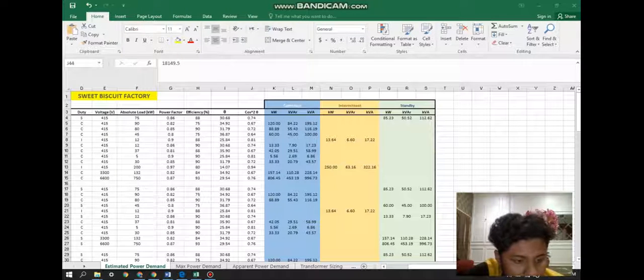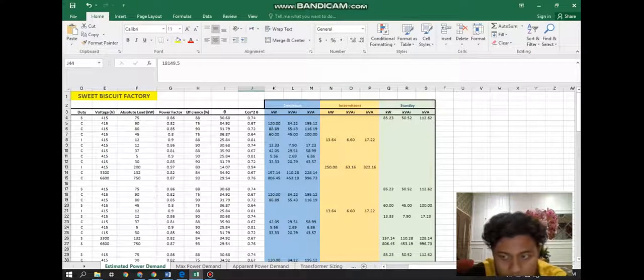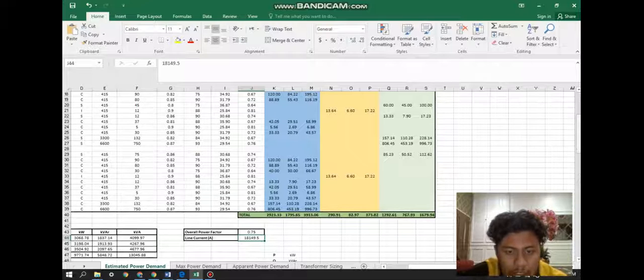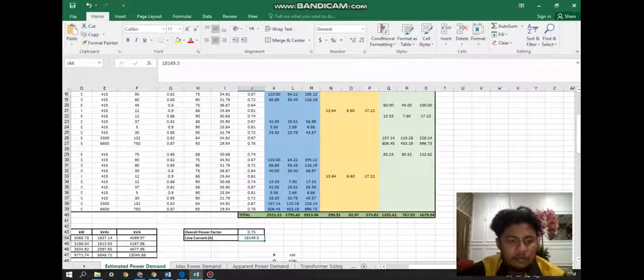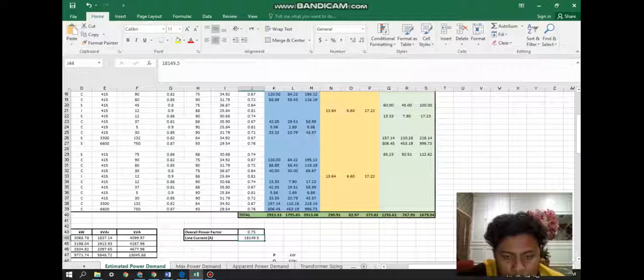Okay. So here I present the estimated power demand. We will use an industrial power network to display the mains, distribution transformers, cables, incoming and outgoing feed lines, and the motor control center, MCC. So as an example in this project, to identify and estimate the overall load demand, the expected power consumption of the industrial power network is shown in the following Excel. It shows that the industrial power network requires 13,045.88 kilovolt-amperes of total apparent power with a minimum supply voltage of 11 kilovolt.